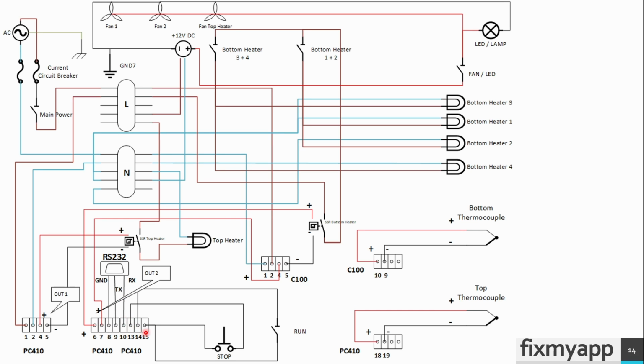On terminal 13 and 15, the stop push button is connected. So when you press this stop button, the program will stop. Between terminals 14 and 15, there will be a switch, a run switch. And when the switch is turned on, it will run the temperature program, the BGA Rework profile. On terminal 18, the positive lead to the thermocouple will be connected, and terminal 19 will be the negative lead to the thermocouple. This thermocouple will measure the top temperature of the top heater.